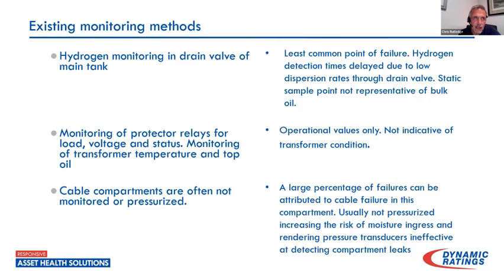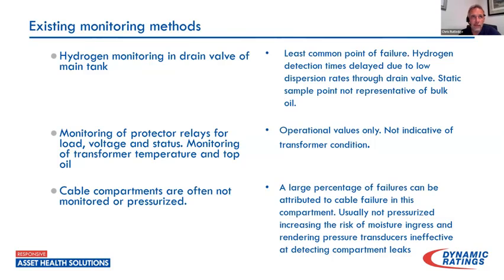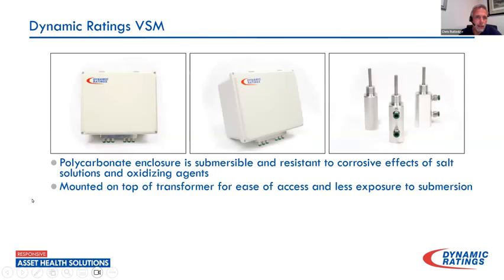I've been in utilities where they've actually put pressure transducers on these compartments. However, the problem is if you have a sealed compartment that's not pressurized, where's the alarm point? Zero would be expected, with some slight variance either side of it. So if there's a leak and all the oil runs out, that's just atmosphere — even with some type of pressure indication, we still don't know remotely that we have a problem. So this is kind of what I came up with.